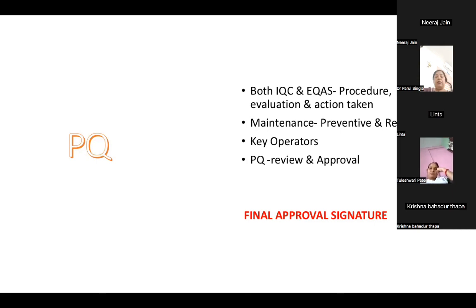If it is not done properly, then you can flag it in the IQ PQ report, that you need to verify this analyte. You have 20 analytes, and in operational qualification you have verified only 5 or 10, but there is another analyte which is misbehaving in IQC and EQAS. You can undergo a complete verification of that analyte on this equipment.